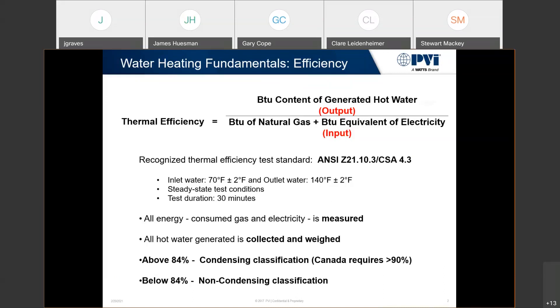It's a 30-minute test where the water inlet is 70 degrees and the outlet is 140, so the delta T across this test is 70 degrees. Industry standard: anything above 84% is considered condensing and anything below 84% is non-condensing — we'll definitely touch on that.